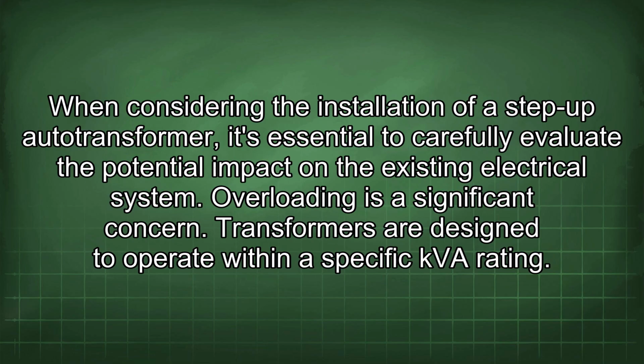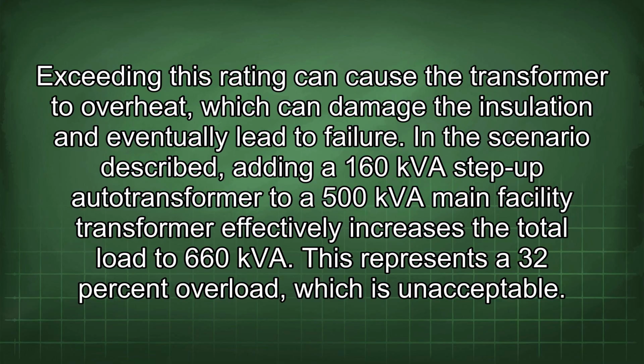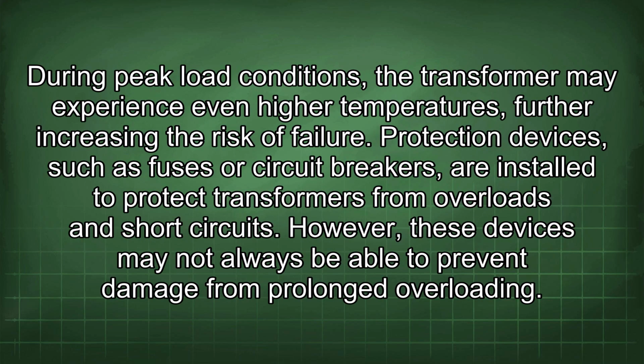When considering the installation of a step-up autotransformer, it's essential to carefully evaluate the potential impact on the existing electrical system. Overloading is a significant concern. Transformers are designed to operate within a specific kVA rating. Exceeding this rating can cause the transformer to overheat, which can damage the insulation and eventually lead to failure. In the scenario described, adding a 160 kVA step-up autotransformer to a 500 kVA main facility transformer effectively increases the total load to 660 kVA. This represents a 32% overload, which is unacceptable. During peak load conditions, the transformer may experience even higher temperatures, further increasing the risk of failure.